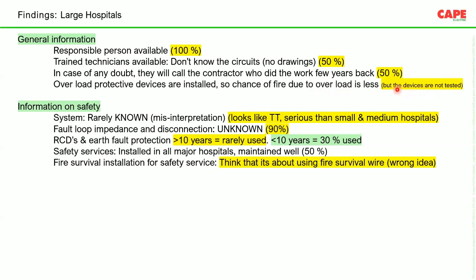You must have seen in the first days of our video that there was a fire in an appliance. The fire became a major fire because the protective device didn't trip. We generally blame fire on overload or short circuit. Actually, the problem is non-disconnection or delayed disconnection of the protective device.